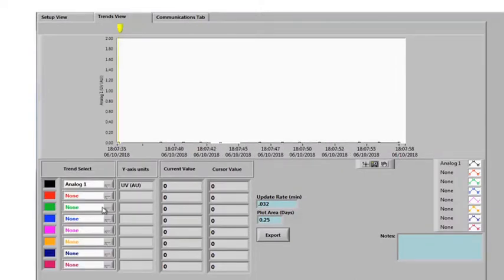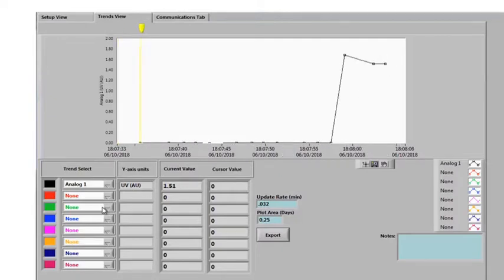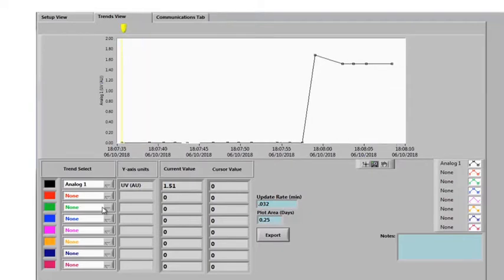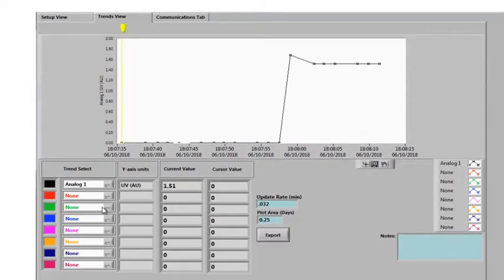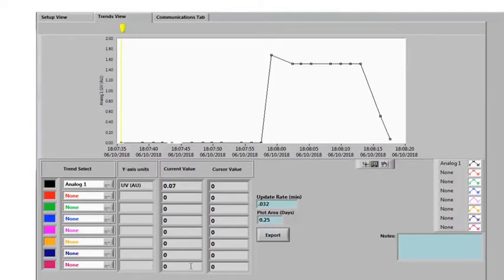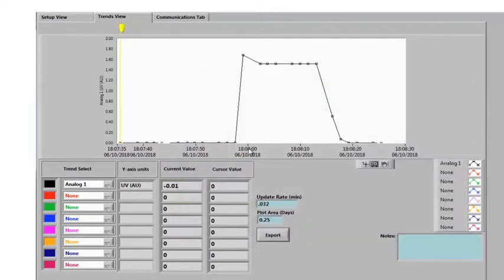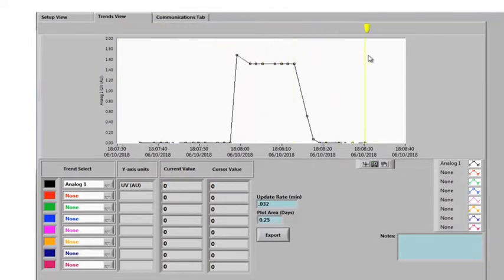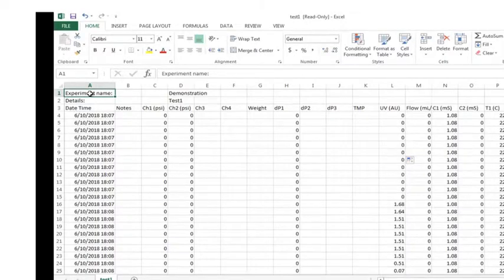The Trends view is loaded with features, including a pick list to choose the data to be displayed and manual or automatic scaling of the X and Y axes. The Trends view allows viewing and documentation of process changes and also demonstrates the responsiveness of the UV photometer to rapid changes in the absorbance as fluid enters the flow cell. Data can be exported for quick analysis, and notes can be entered that are logged into the data file. Past readings can be viewed by moving the yellow cursor. The data file is opened with Excel, and the recorded data and notes can be viewed.